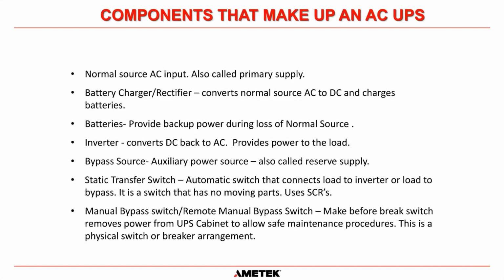The next block is the static transfer switch, and that's an automatic switch inside the UPS that connects either the load to the inverter or the loads to the bypass. It is a switch, but it has no moving parts, so there are no contacts inside the switch. We use SCRs, which are semiconductor devices. They're silicon-controlled rectifiers, and all we need to do is send an electronic signal to them, and they turn on instantaneously, and that way we can transfer between inverter and bypass seamlessly without a break in power.